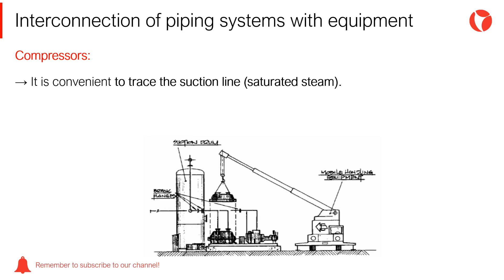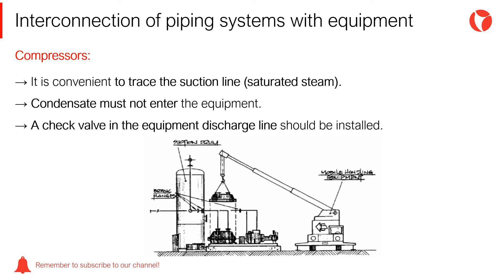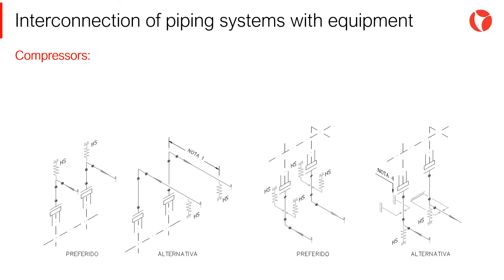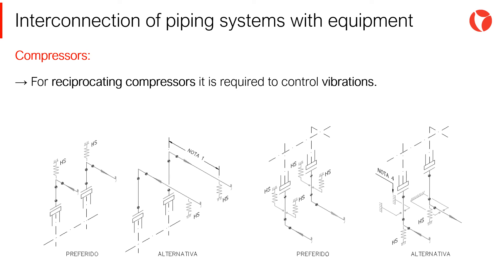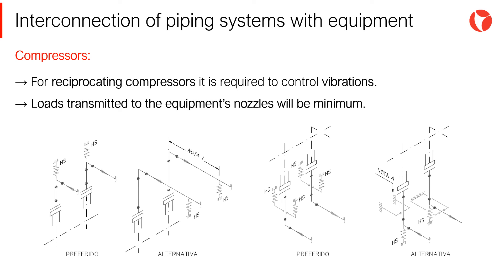It is convenient to trace the suction line of the equipment with saturated steam. Condensates must not enter the equipment. A check valve in the equipment discharge line should be installed. For reciprocating compressors, it is required to control vibrations, and loads transmitted to the equipment nozzles must be minimum.